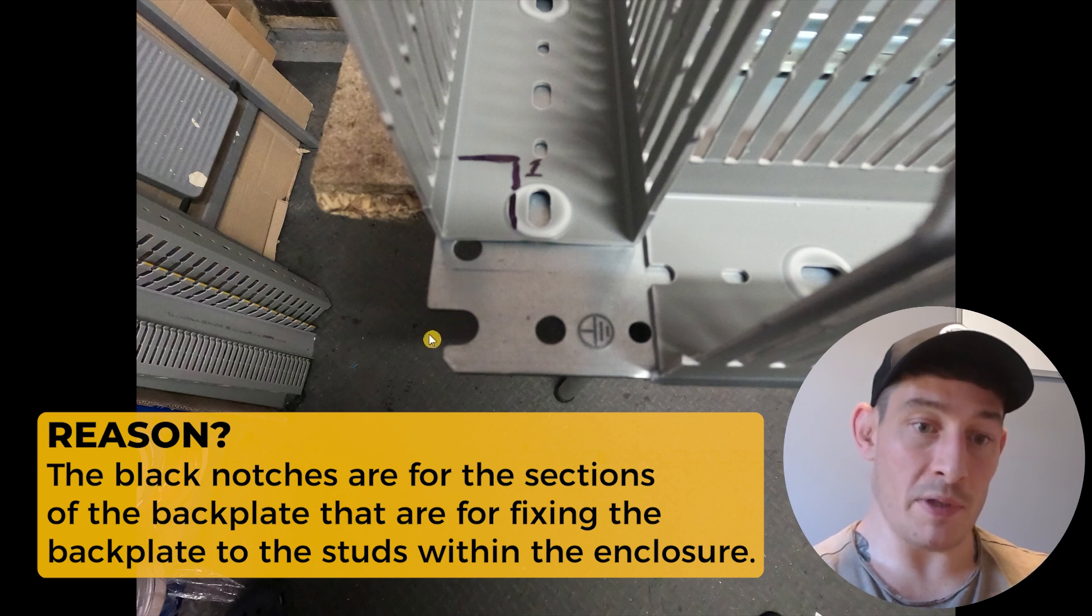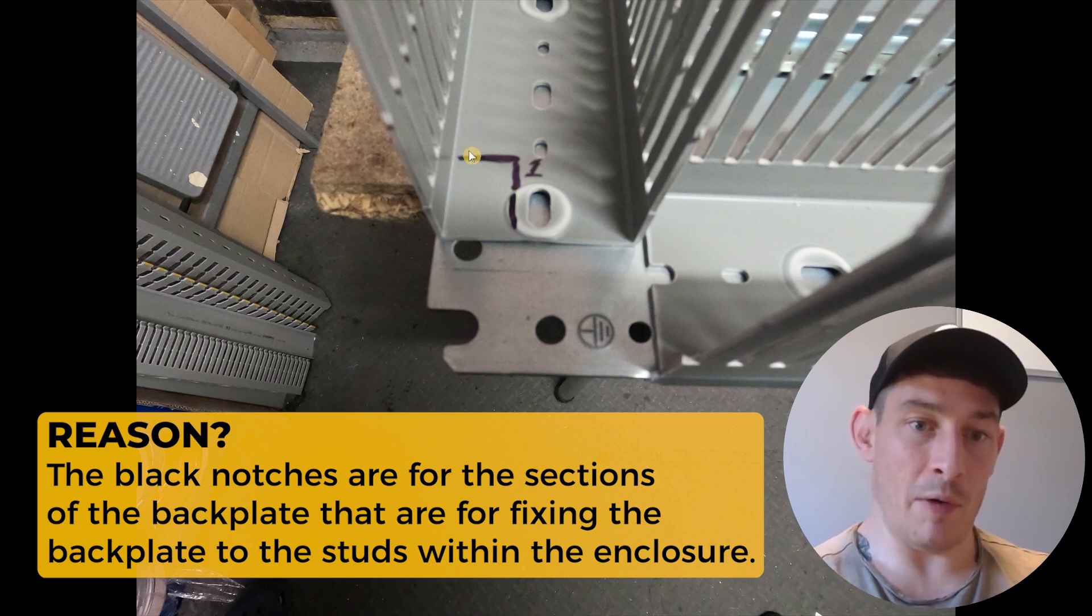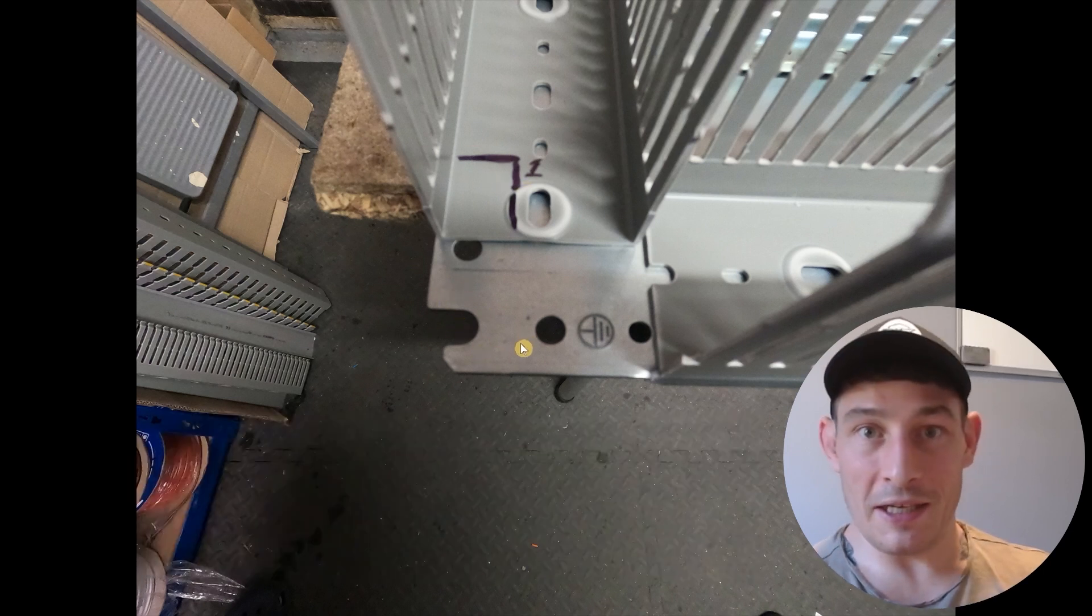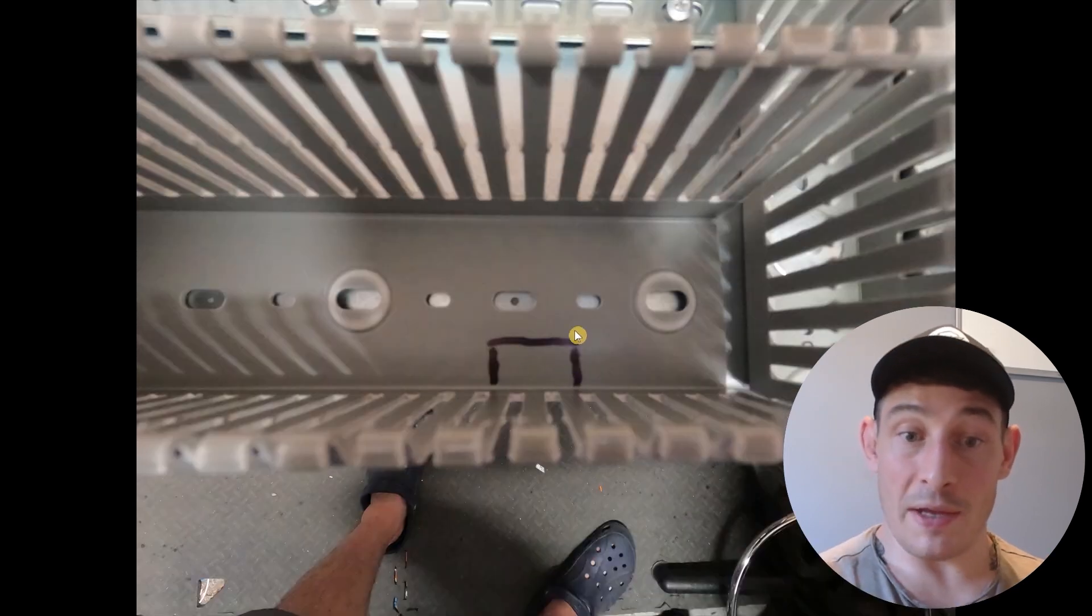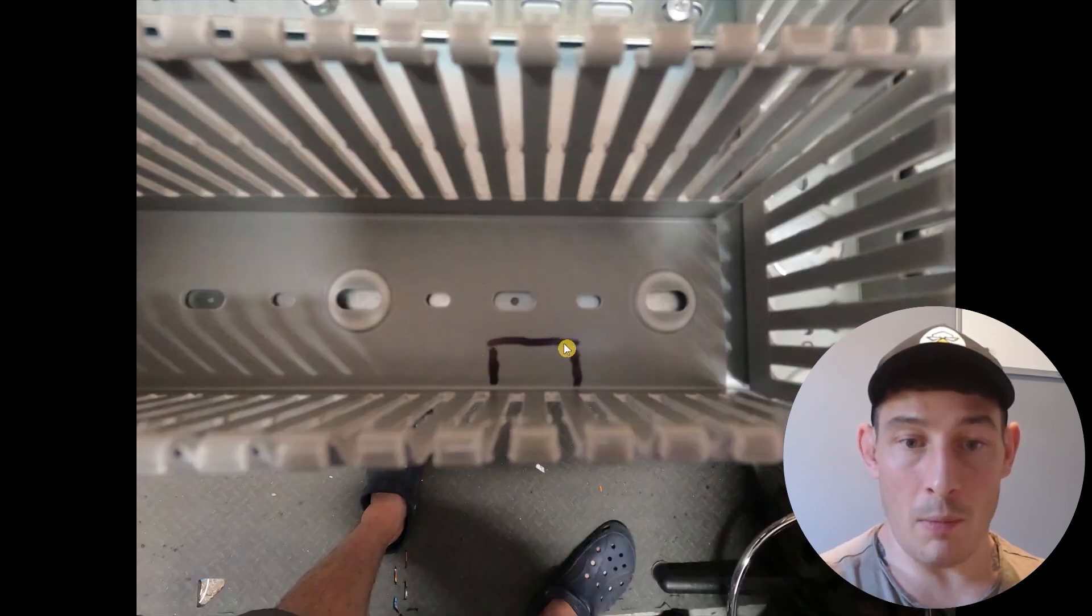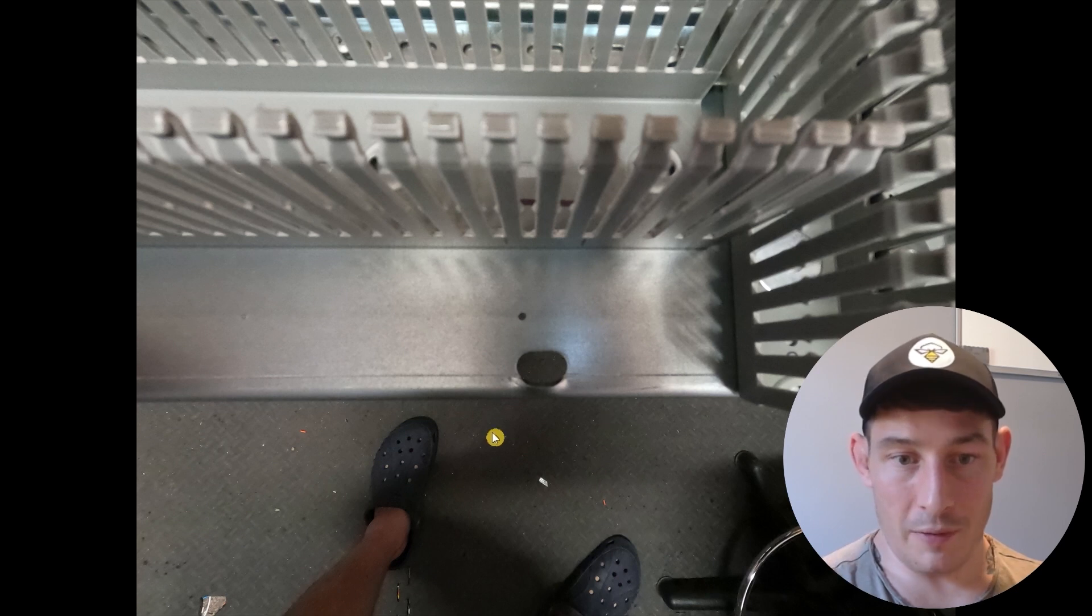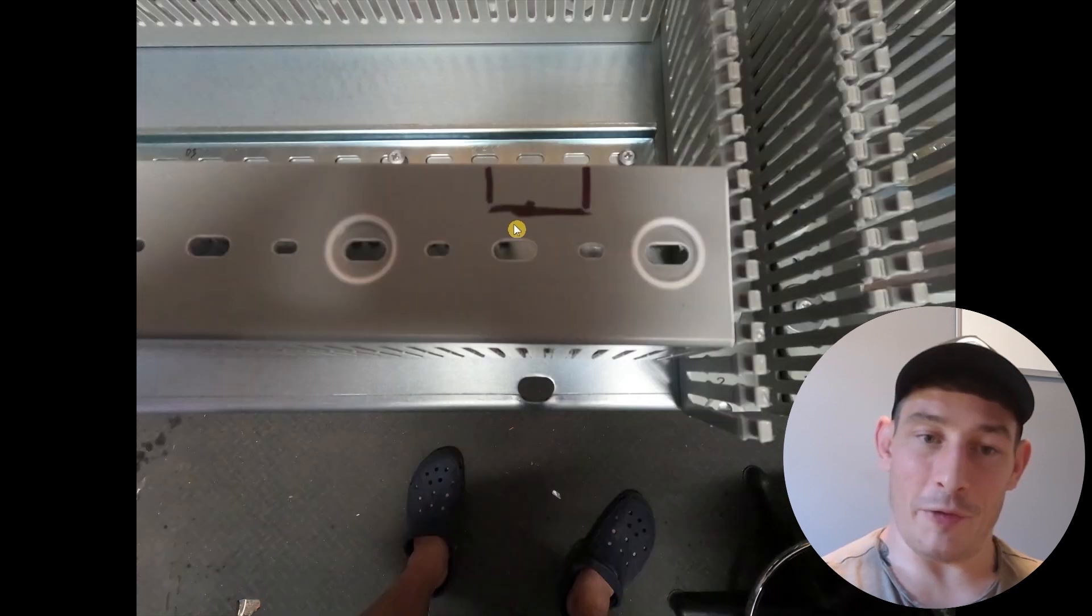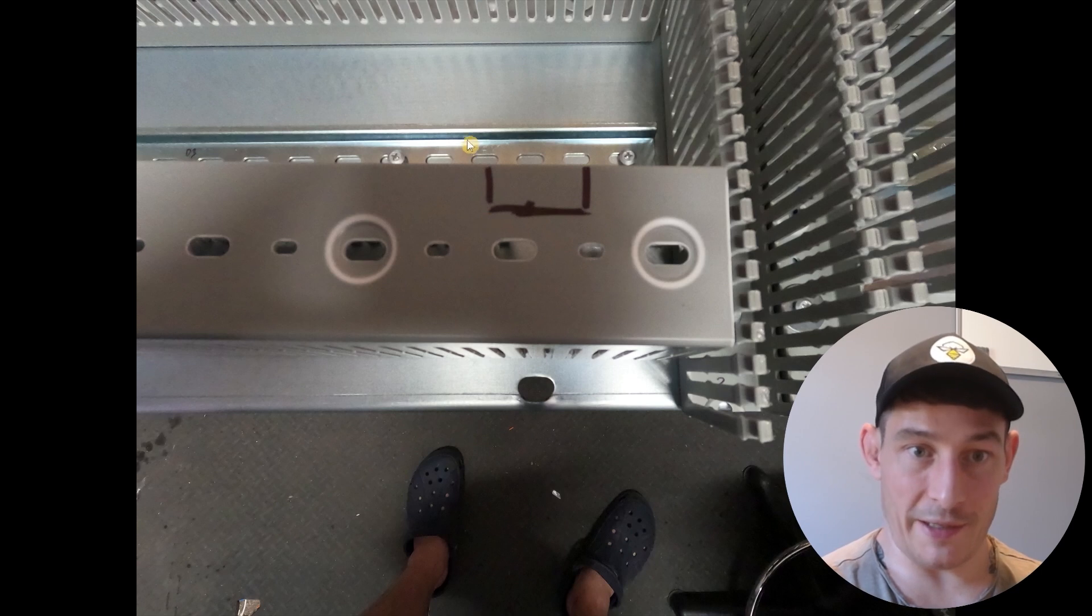Therefore fixing the back plate to the studs within the enclosure, so a stud will come through here and then we'll be putting a nut on the end of that and we obviously don't want finger trunking being in the way. So there's one of the middle cutouts so I'll mark something like that, enough to allow space around this fixing hole.